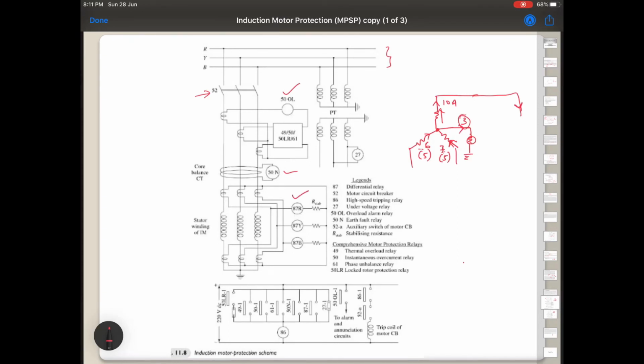Now we have a differential relay here. How this operates is, this 87 is a differential relay for R phase, Y phase and B phase separately. Actually, since we had taken a single line diagram, we were considering one relay, but for each phase separate relays are always there. So how the differential relay works is, suppose there is a fault inside the rotor or stator, the high current has to flow here, and maybe inside or outside, any direction, it depends.